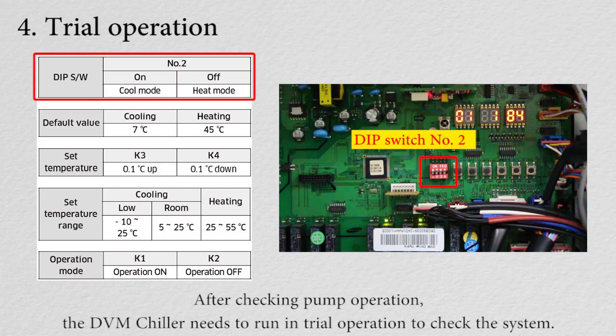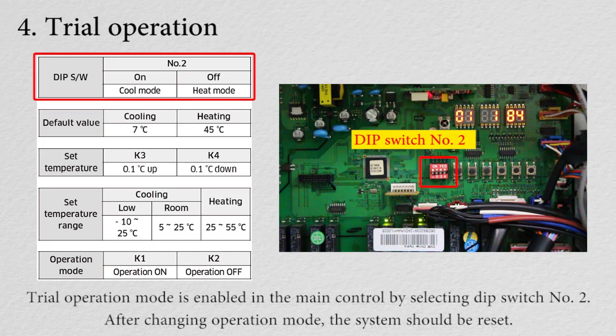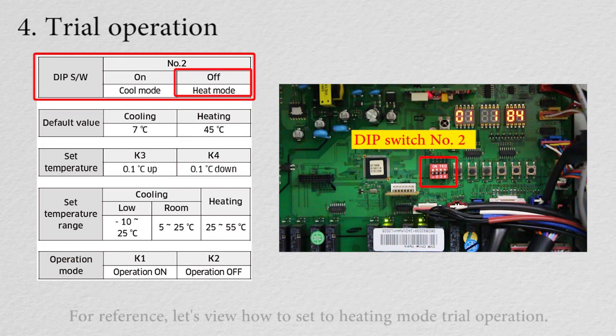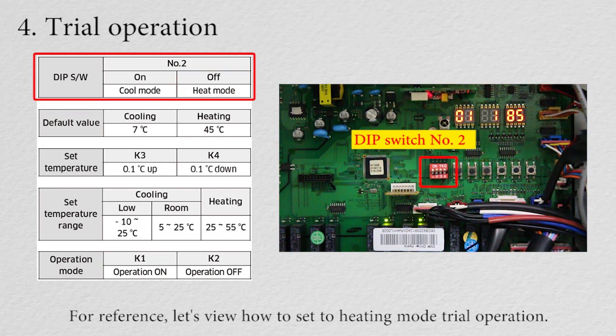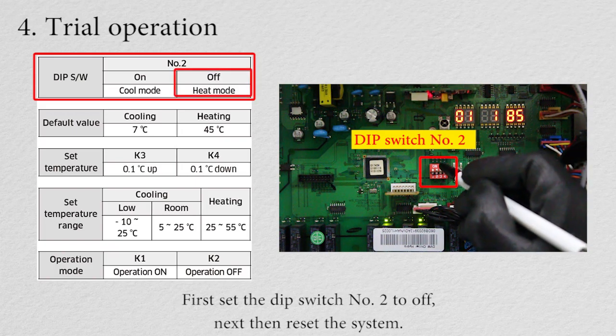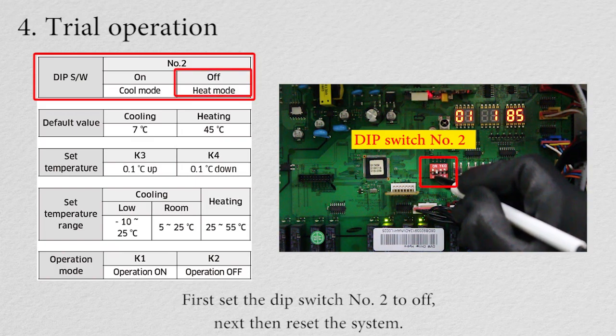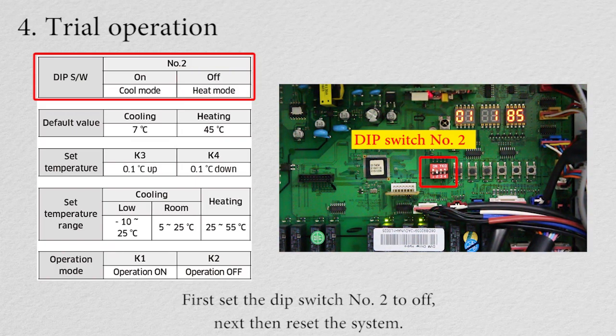After checking pump operation, the DVM chiller needs to run in trial operation to check the system. Trial operation mode is enabled in the main control by selecting dip switch number 2. After changing operation mode, the system should be reset. For reference, let's review how to set heating mode trial operation. First, set dip switch number 2 to off. Next, reset the system.